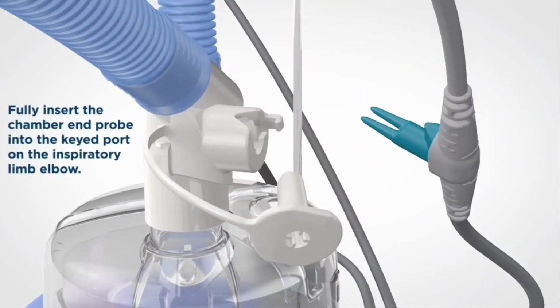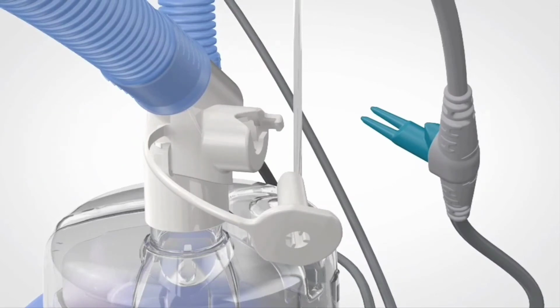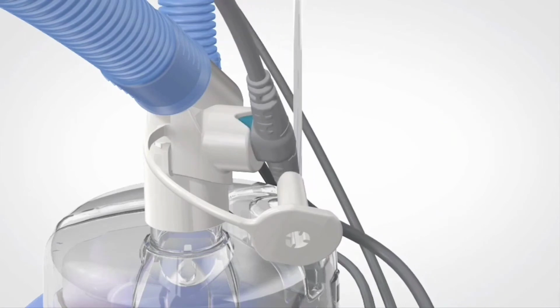Connect the temperature and flow probe to the port in the side of the elbow connector. The probe port includes a V-shaped notch corresponding to a V-shape on the probe. Line these up and push the probe firmly into place. In adult breathing circuits, there is a latch. Infant circuits use a friction fit. It is important for correct operation of the humidification system that the probe is lined up with the V-notch and inserted fully.